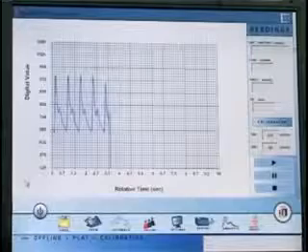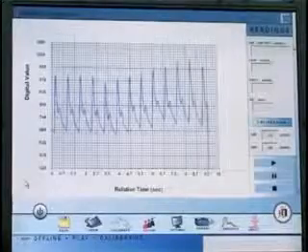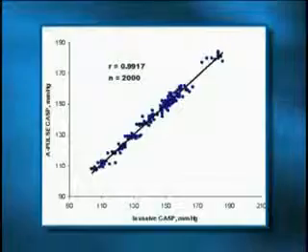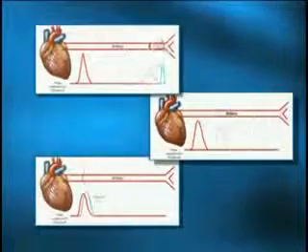Now, when we did that invasive method using a protocol written by Professor Brian Williams, he used a catheter and put it at the root of the aorta, and we put the BPro on the hand of the patient undergoing angiogram. For every wave, we continuously followed wave for wave. We measured the central pressure here, and we read off the central pressure as calculated by the A-Pulse. We have 2,000 patient waveforms, and the accuracy was 0.9917, which is unbelievable.